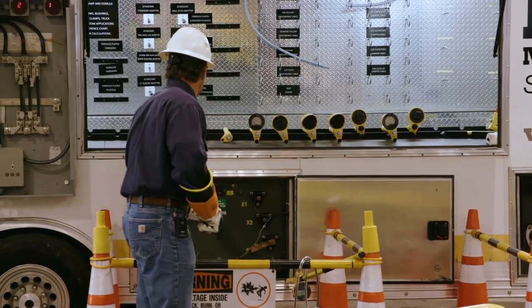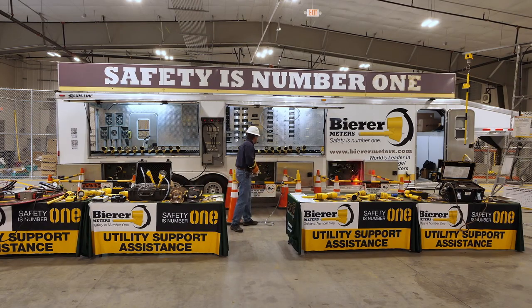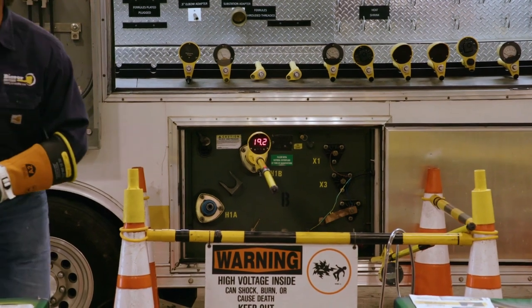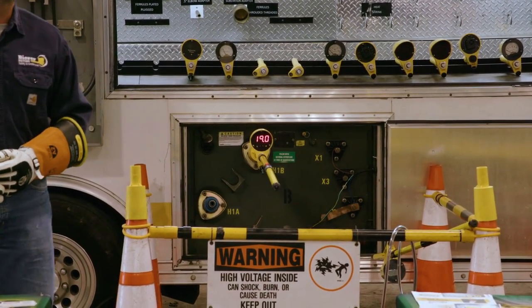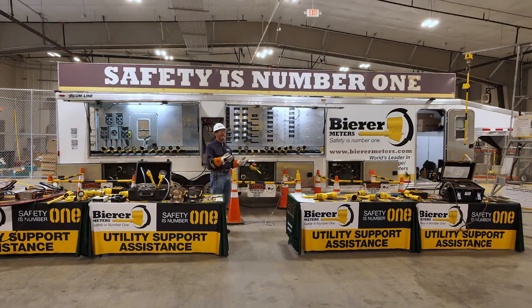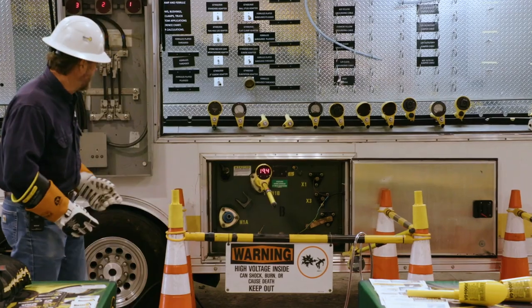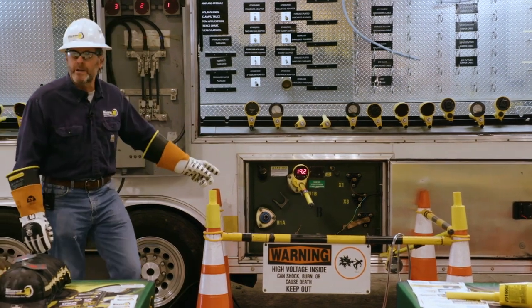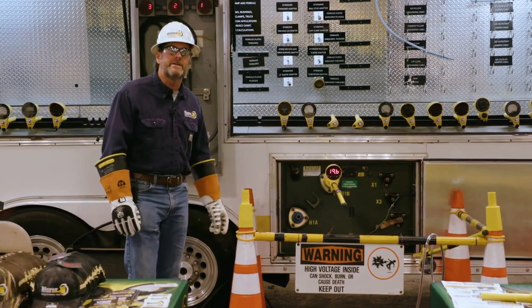Direct contact. So we're getting about 20,000 volts, pretty accurate tool. When you're using your tools, you're always gonna use it on a live known voltage source prior to use. You wanna make sure the tool's functioning properly and is calibrated properly. So we're using it on a live known voltage source before we open the switch. Remember, the battery test doesn't test the tool functionality, okay? So we know our tool's working pretty good, about 20,000 volts, pretty accurate.